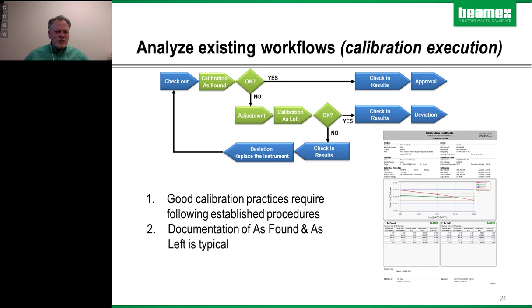So that's one resource you have. You can also sort of self-audit. How do you execute a calibration today? So here's a little workflow. You do an as found. If it passes, you check it in and it's approved, and maybe you file your paperwork some way. But if an adjustment has to be made, then you do an as left test. If it's okay, it's kind of similar, but you've had a deviation. If you can't get it to adjust, then how do you issue a repair or replacement work order?